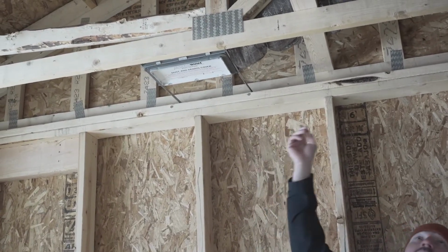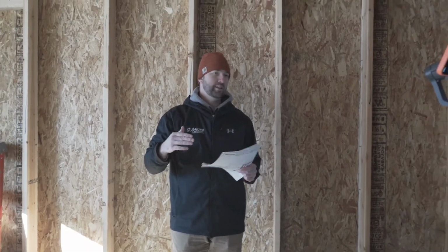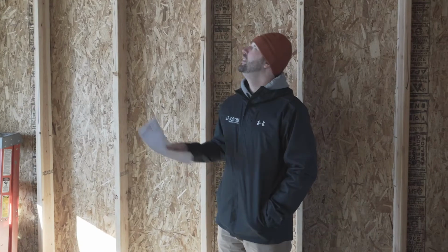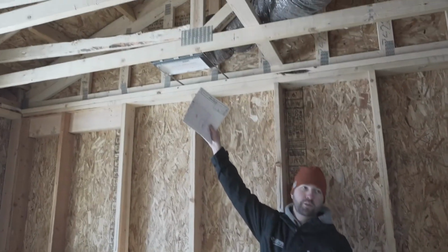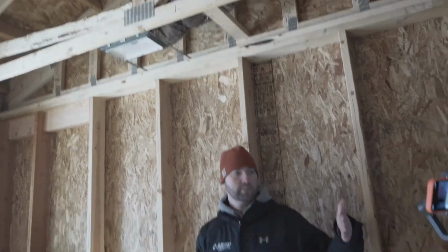This is flex duct up here, which is required to have an R value when you're up in an attic space. When you're down in conditioned space, like in between floors, like your basement and your main floor, that's when we're running sheet metal, and insulation is not really required. Here's a supply boot, which would be blowing out air. And then usually on the walls, horizontally or vertically, are your returns, which suck air back to your system.